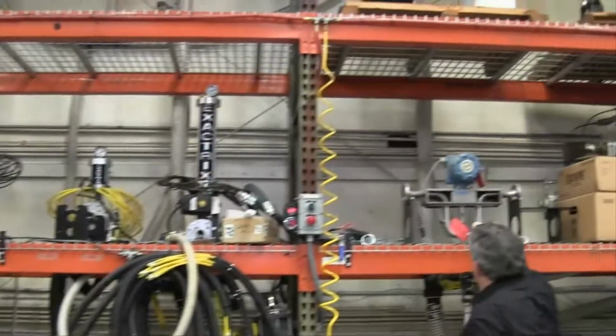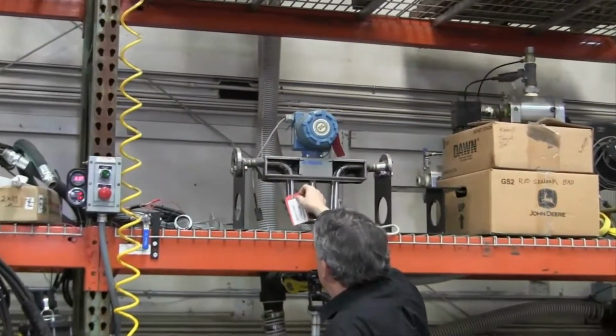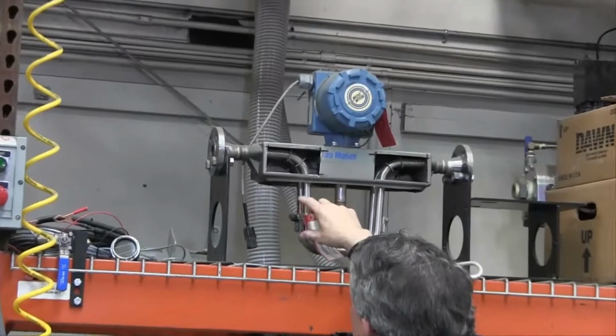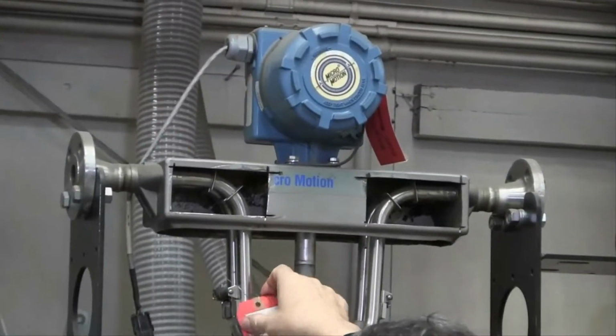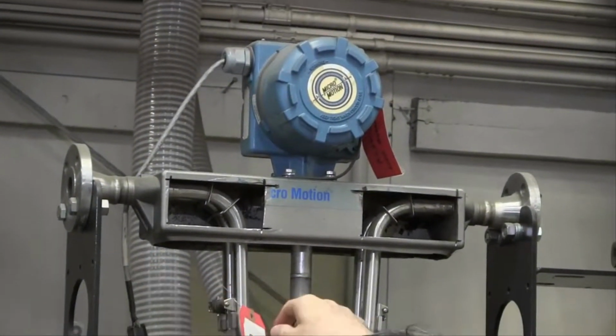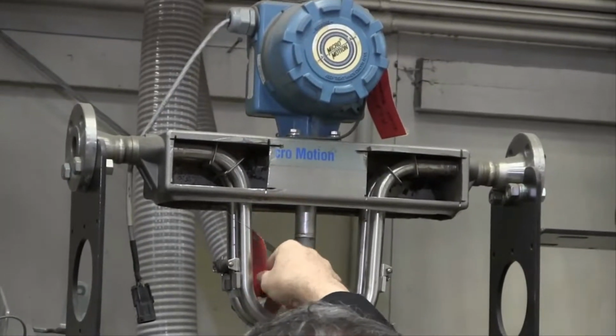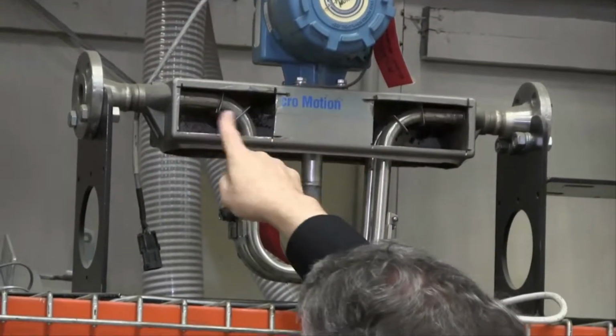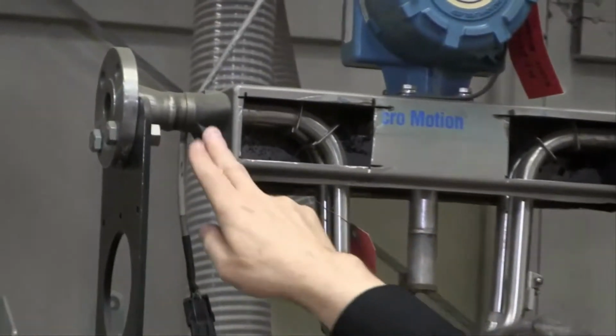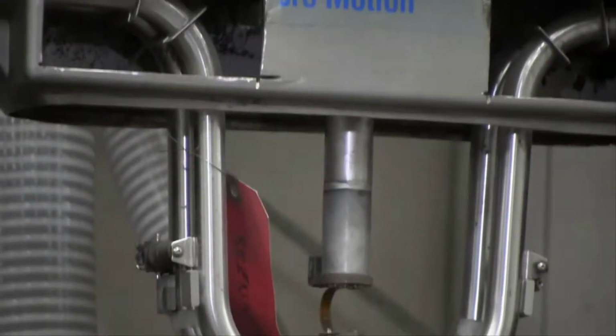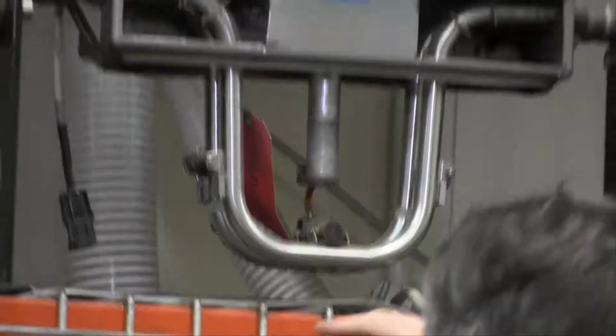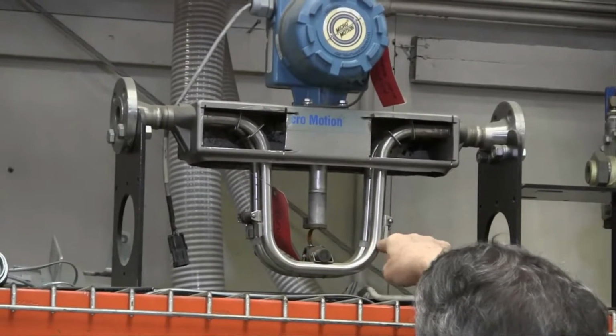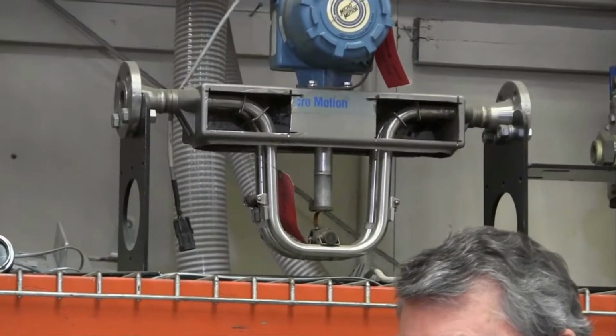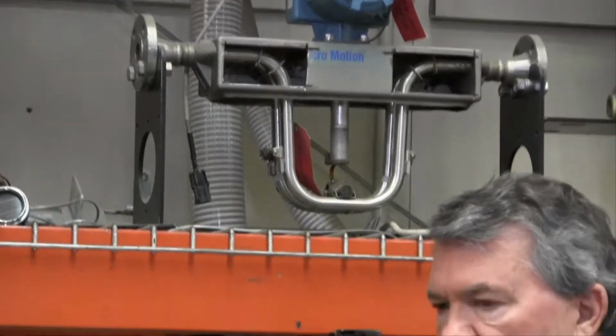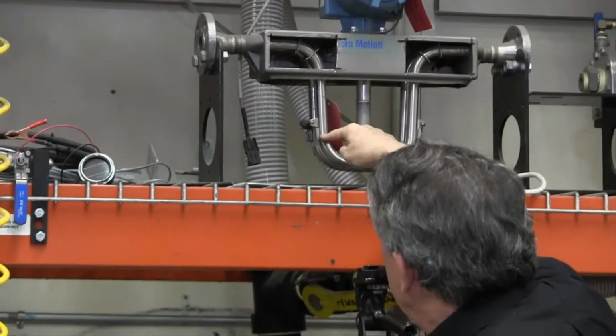And here is a mass meter that was destroyed in the field and got hit by something flying. It flew into it, so we cut it apart, and you can see here the dual tubes and what's inside that meter. The flow comes in and the tubes are split, so there are two tubes and they are actually waving at each other, and there are transducers that pick up the signal, and as the flow rate changes, the signal changes because of the torque or the rotation.